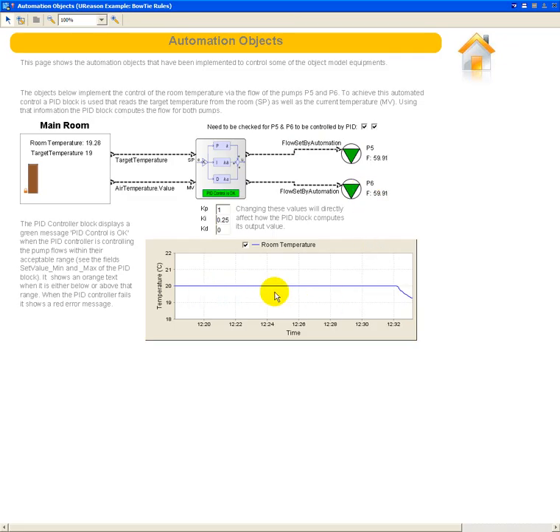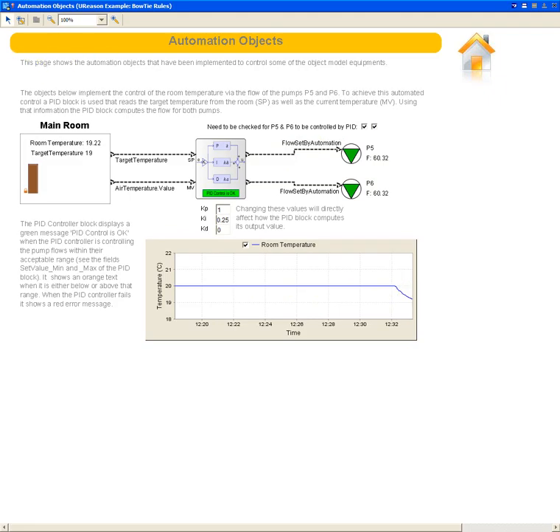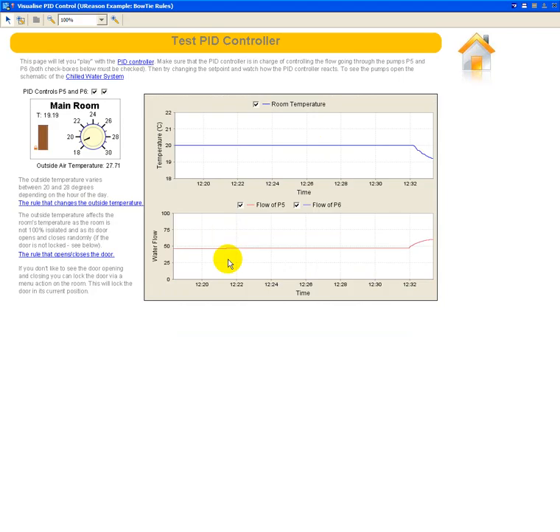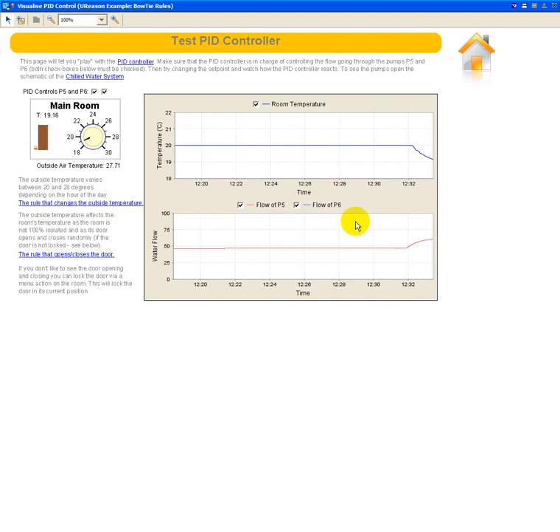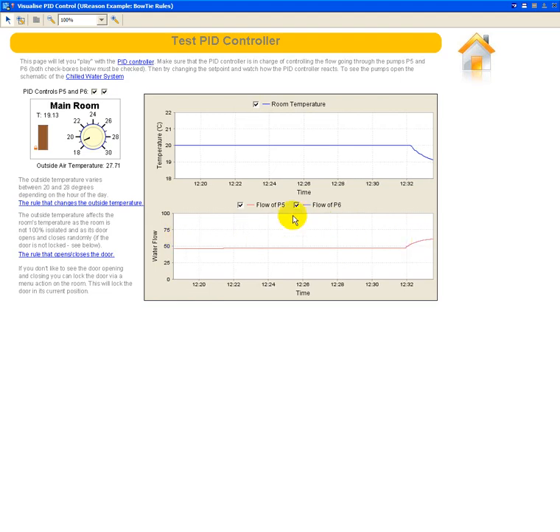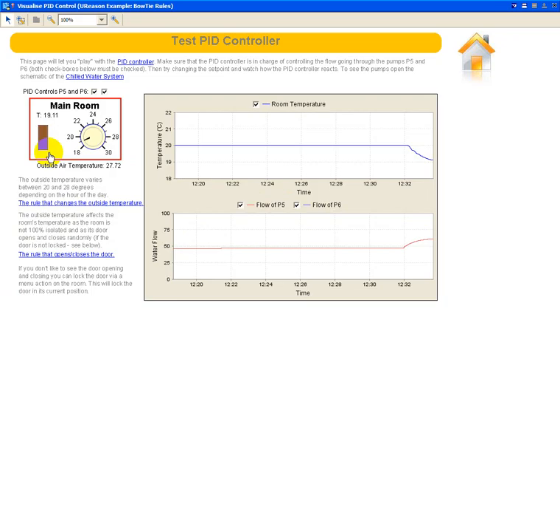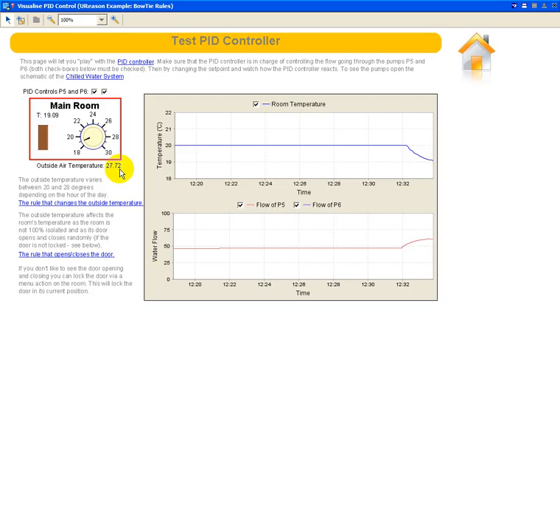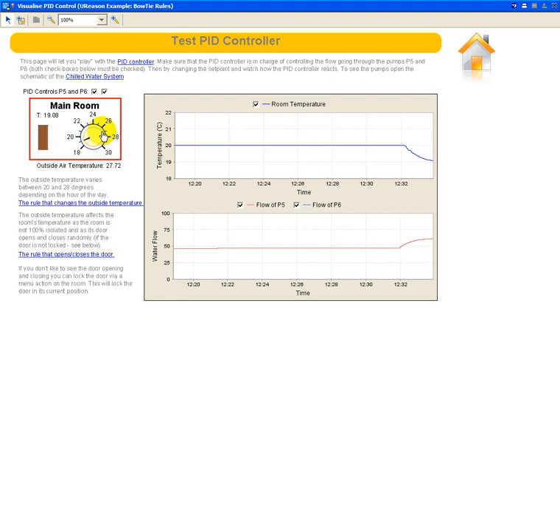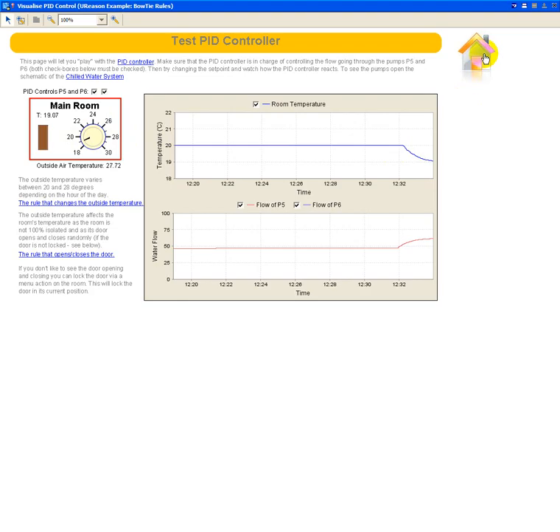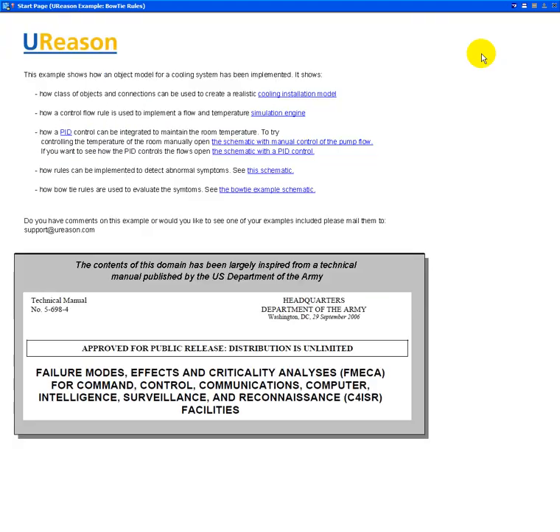And we see now that the temperature is slowly going to adjust itself around the 19 degrees. So if I go back to the screen here, we see that the PID has decided that the flow of the pump now should be around 60 or something like that. We can make the life of the PID a bit more complex by opening and closing the door here. The room is not completely isolated, so if I unlock the door of the room, there'll be more hot air coming inside the room. And in that case when the isolation of the room is not 100%, the PID will have to regulate that part of the temperature also.